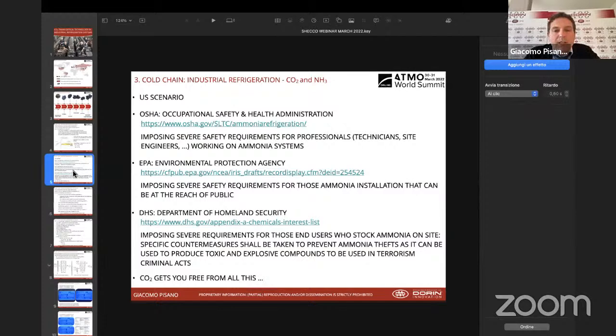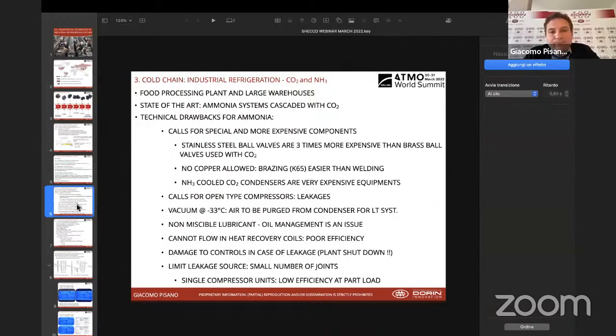Basically, with CO2, it can be dealt with much more easily. Clearly, with CO2, you still need to pay a lot of attention to the use of that refrigerant, because it can be troublesome to a certain extent. But clearly, there are some differences with ammonia. From an ammonia standpoint, there are also other drawbacks that are more technical and not only relating to safety. Ammonia calls for special and expensive components. You normally need stainless steel everywhere, including ball valves that are quite expensive. No copper is allowed, while with CO2, you can also use K65 and brazing, which is easier than welding with stainless steel.